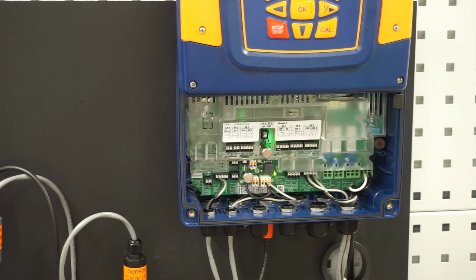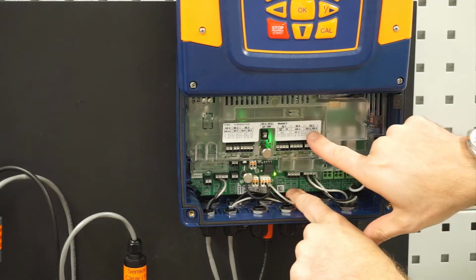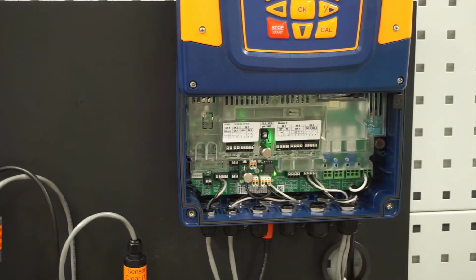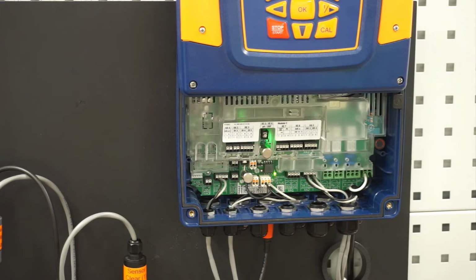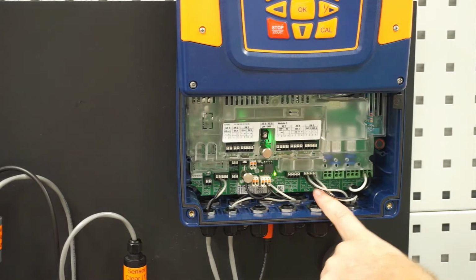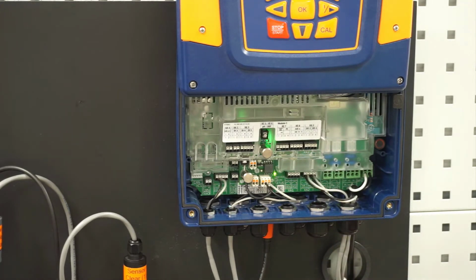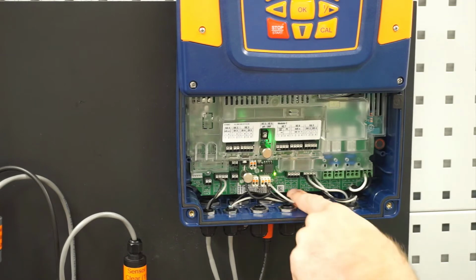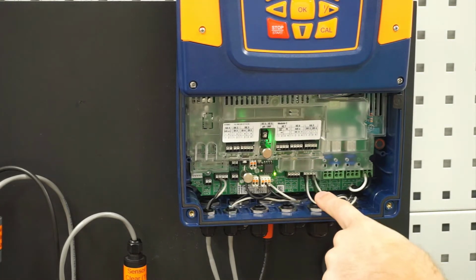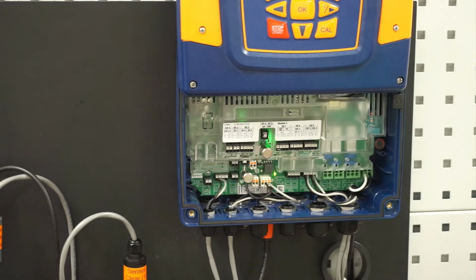The nice thing about those is there's two here, and then there's also two up top on the top board. Our ProMinent pumps, for the most part, come standard with the ability to take a contact into it. So we could just use our universal control cable, bring it in, wire it into our digital outputs, and control directly from here. You also can control with your milliamp outputs, but typically for a ProMinent pump, getting a milliamp signal into that pump is an adder to the price. So we can just do it with the digital outputs, and that would free our milliamp outputs up, and we can just use those as a measured variable instead of a control variable.